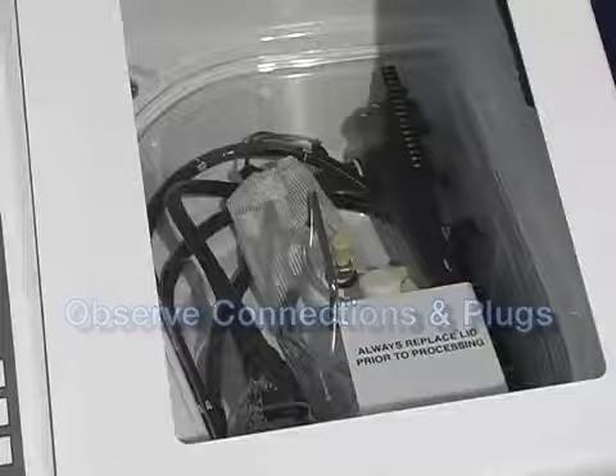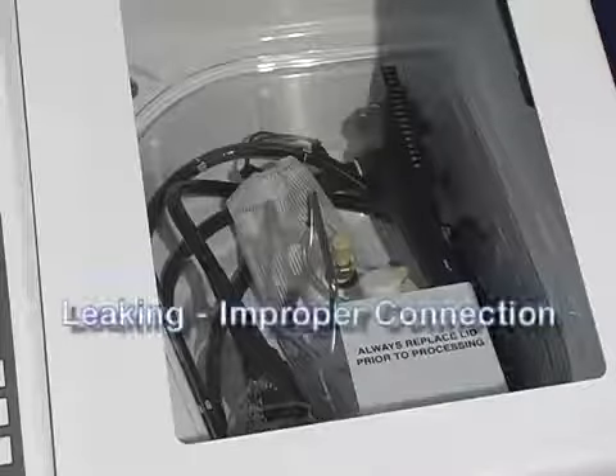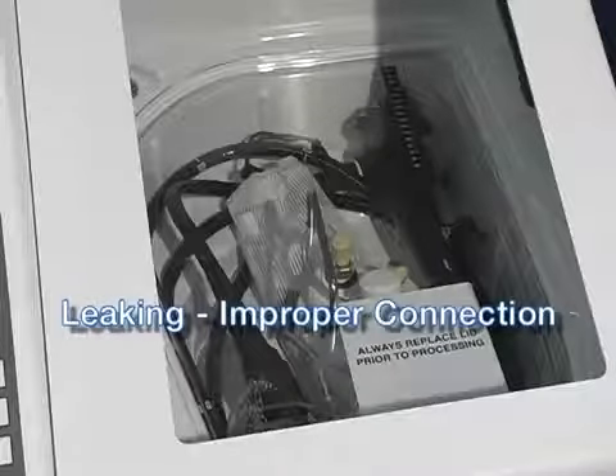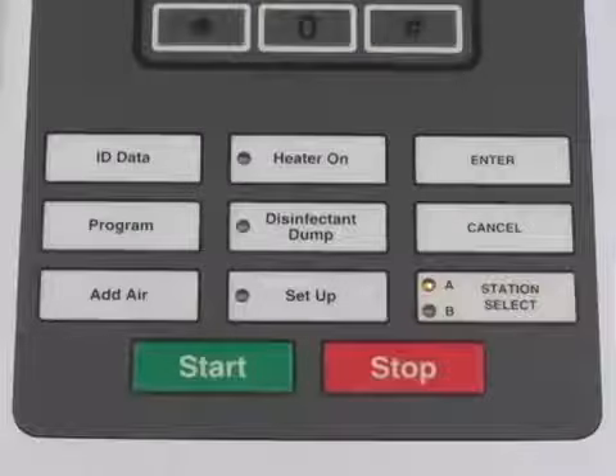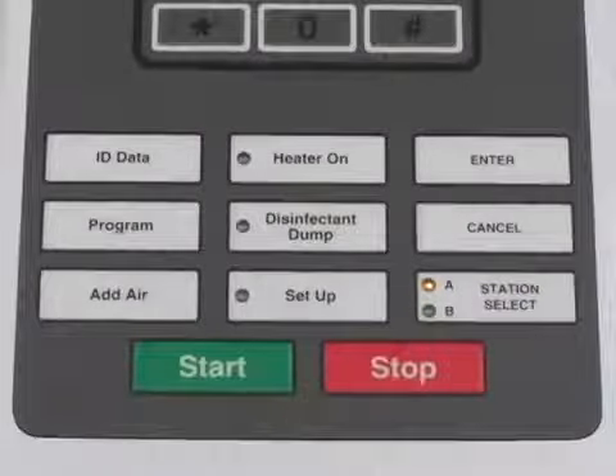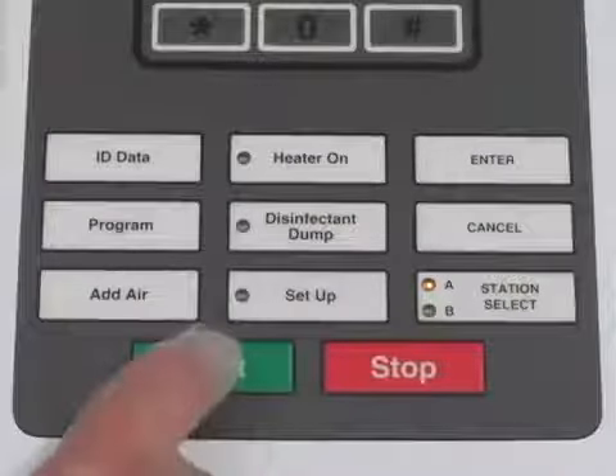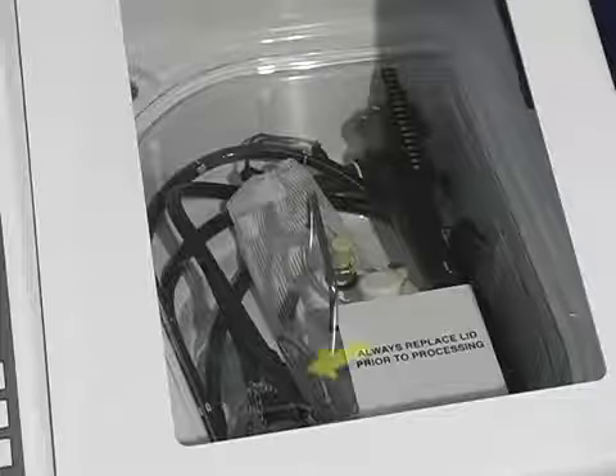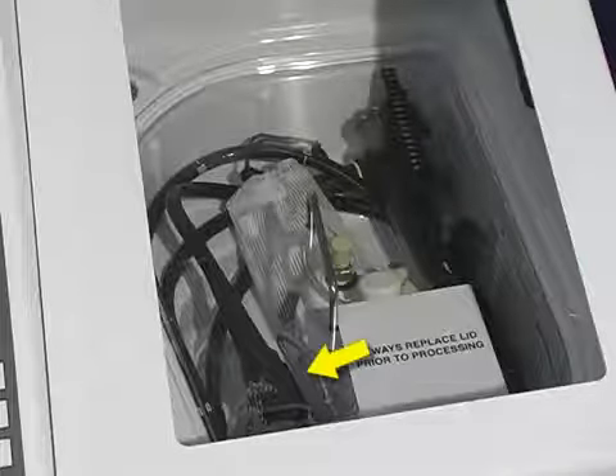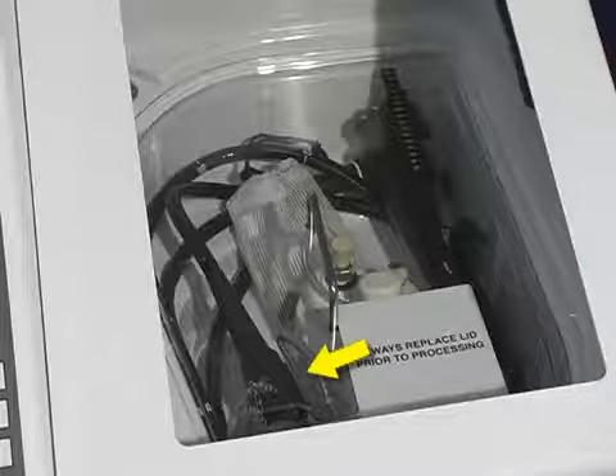No other connections should leak. If leaking is detected, it is usually a sign of a bad connection. Select the appropriate station. Press Stop to correct the problem. Press Start to resume. Observe the connection at the light guide connector and ensure that liquids are moving through the connector. Verify that liquid exits the distal end of the endoscope. If there appears to be any blockage, the endoscope must be manually re-cleaned.